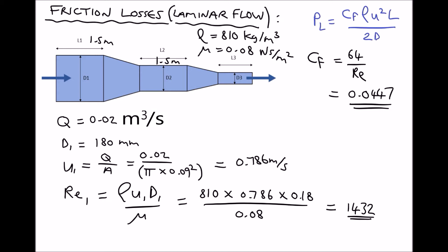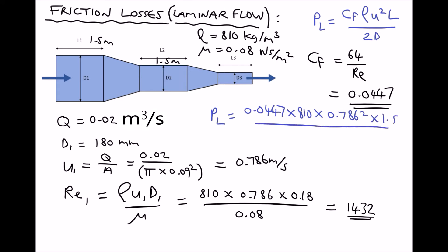The final step is to plug everything into our formula. The pressure loss equals the coefficient of friction 0.0447, times the density 810, times the velocity squared 0.786 squared, times the pipe length 1.5 meters, all divided by 2 times our diameter — remembering to work in meters — so 0.18. Running that through the calculator gives us a pressure loss in the first section of the pipe equal to 93.20 pascals.